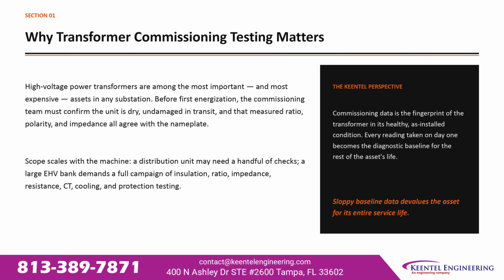High-voltage power transformers are among the most important and most expensive assets in any substation. Before first energization, the commissioning team has to confirm the unit is dry, undamaged in transit, and that measured ratio, polarity, and impedance all agree with the nameplate. Scope scales with the machine. A distribution unit might need a handful of checks. A large extra high-voltage bank demands a full campaign of insulation, ratio, impedance, resistance, CT, cooling, and protection testing.